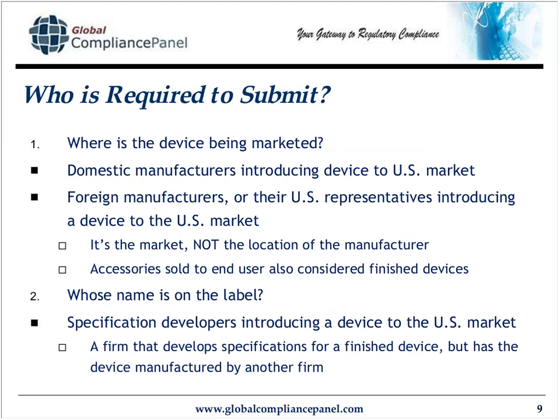When it comes to, do I need to submit a 510K, there are several questions that need to be asked. The first question is, where am I marketing the device? If I'm a domestic manufacturer introducing a device to the U.S. market, sure, I do need to submit a 510K. If I'm a foreign manufacturer, or maybe a U.S. representative of a foreign manufacturer, perhaps a branch or a subsidiary, and I'm introducing a device to the U.S. market, yes, I do need to submit a 510K. It's where you're selling the device. It's the market, not the location of the manufacturer.